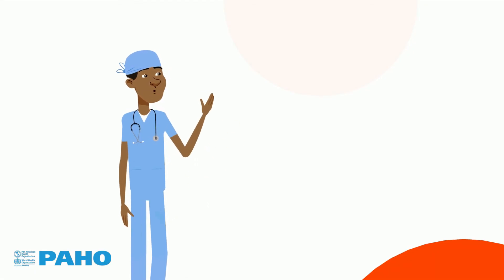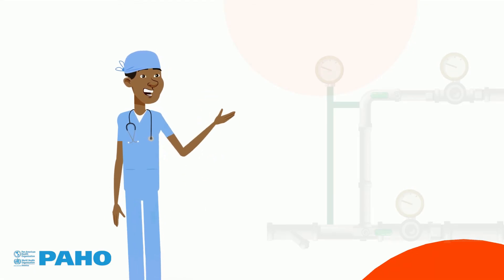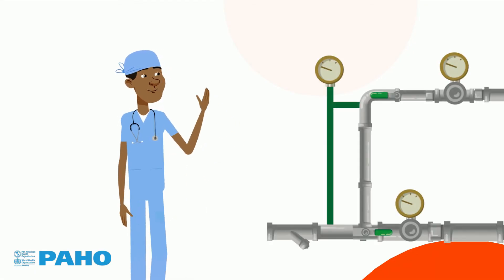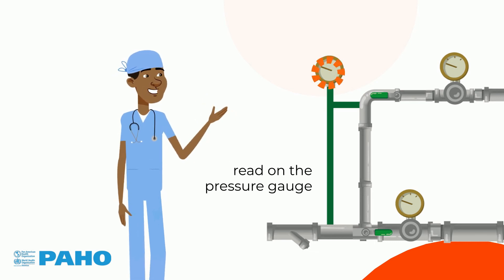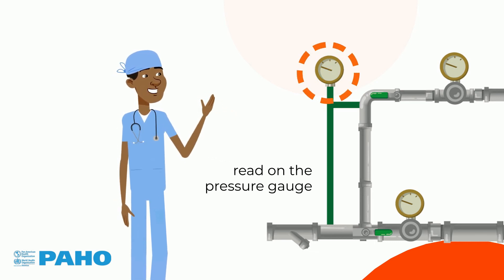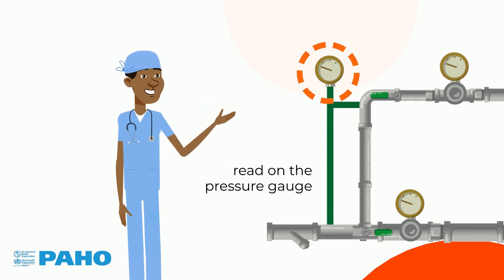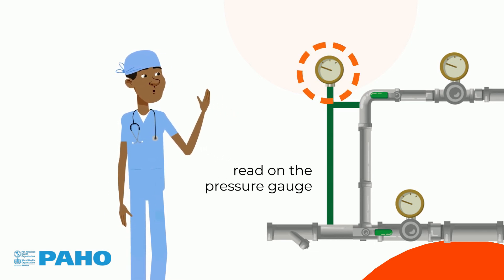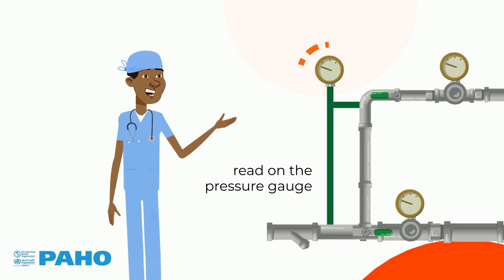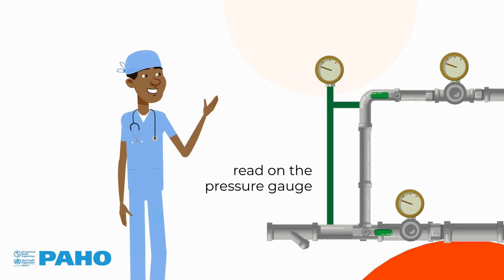The pressure in the evaporator circuit can easily be read on the pressure gauge. If the pressure decreases, it may be necessary to defrost the evaporator.